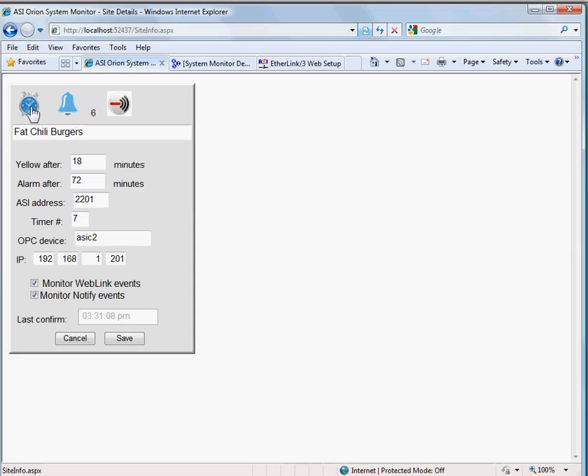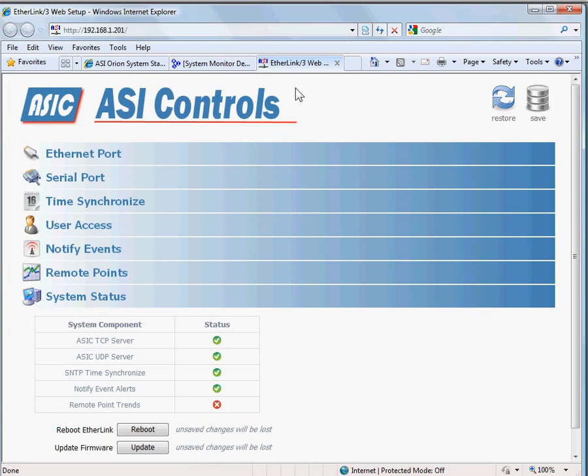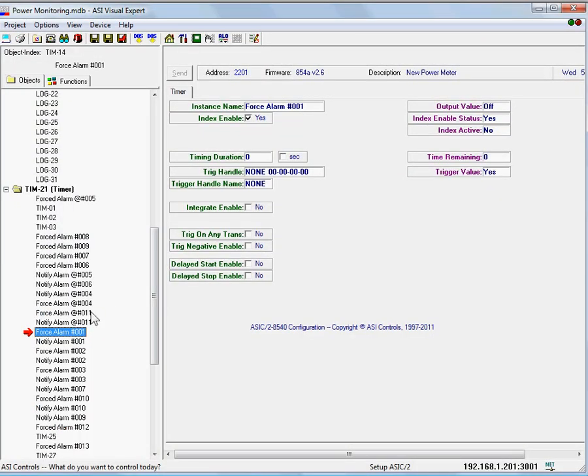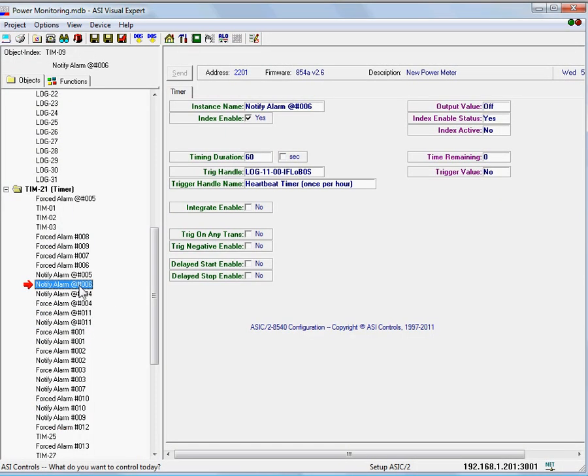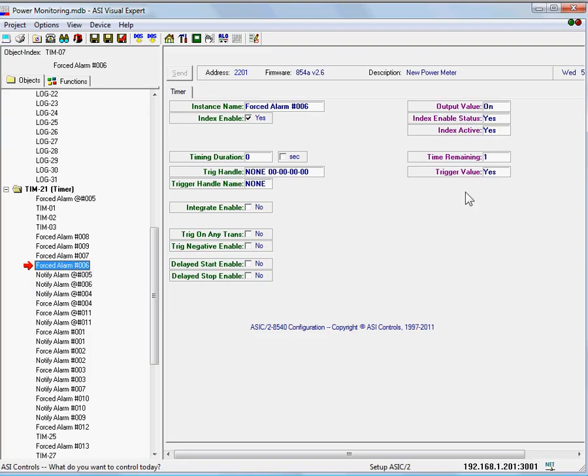We'll look for number six, and we'll look for forced alarm, and there it was just counting down. So we can see how that push button on the front end on the browser triggers a notify event out of the controller.